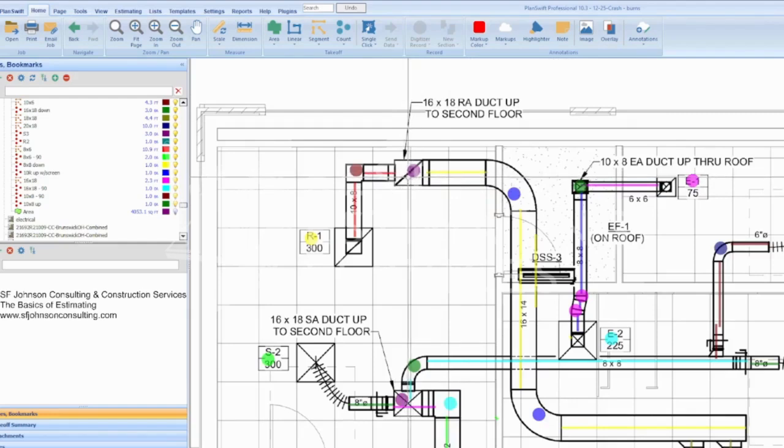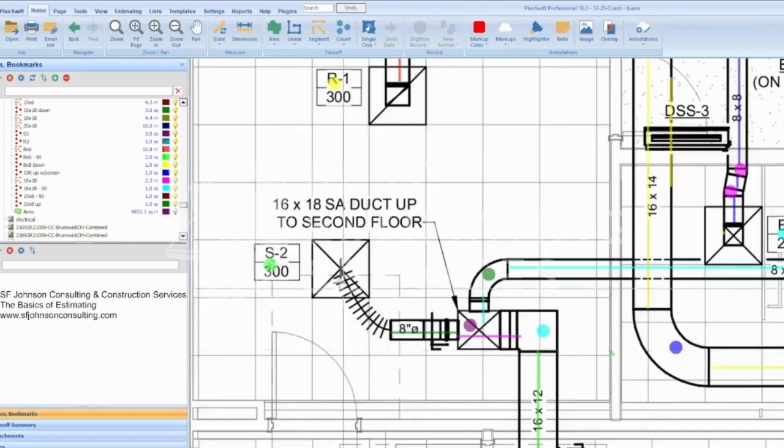Your ductwork is rigid, so you have to have straight pieces and then connected to 90-degree pieces, and it's not flexible. The only portion of flexible ductwork you can allow to use are at the grills, and this is a symbol for a flexible ductwork, and it's usually no more than like 5 feet, max 3 to 5 feet. So that's what that means.